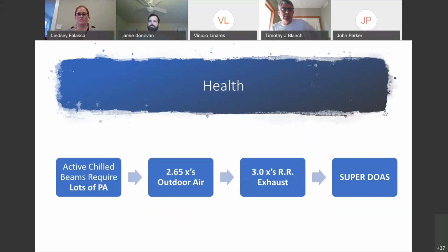And so we wrestled with this, and we decided, well, it sure would be a lot simpler if our building had one type of air in it. But if you're going to bring a lot of outdoor air in, you're going to have to exhaust a lot of air. So what we did is we design and operate the restrooms at 3 times code. So instead of 75 CFM per fixture, a toilet, it's 225. So if you have 4 toilets in a typical restroom in this building, men's and ladies, that would be set at 300 CFM. We operate at 900, which is pretty wonderful.